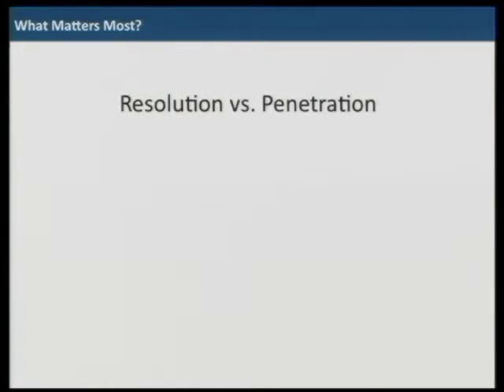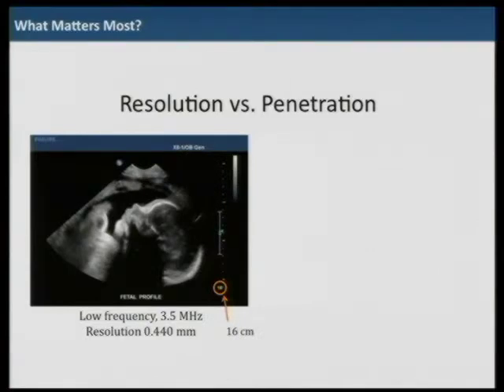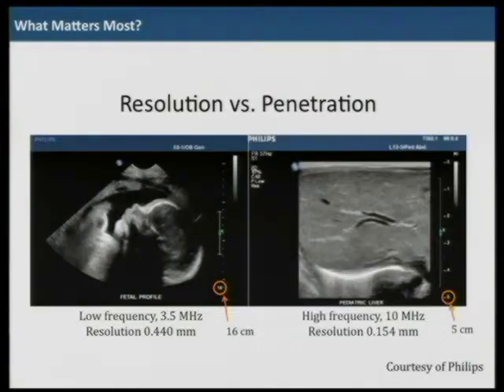Resolution and penetration are always a trade-off, and that matters most. With low frequency — if you look at this image — at 3.5 MHz, the resolution is about 0.4 mm and penetration about 16 cm. But with 10 MHz, you can achieve much better resolution of about 0.1 mm, but penetration is limited to about 5 cm. So our goal is to achieve good resolution with acceptable penetration.